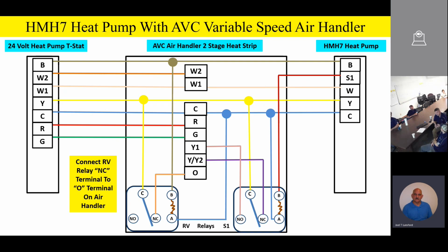However, when we go into the heating mode of operation, we've got to break that O terminal. So you'll see the way it's wired right now that when we energize the B terminal for heating on the heat pump, it'll energize that RV relay and it's going to break that O terminal, and that's exactly correct.